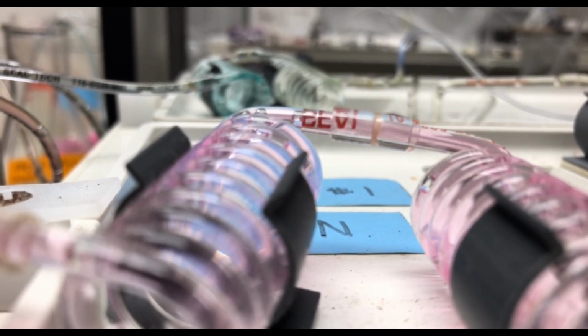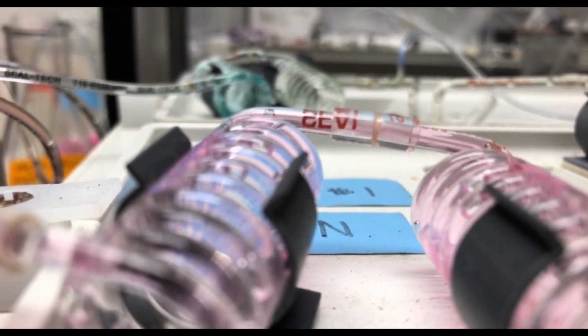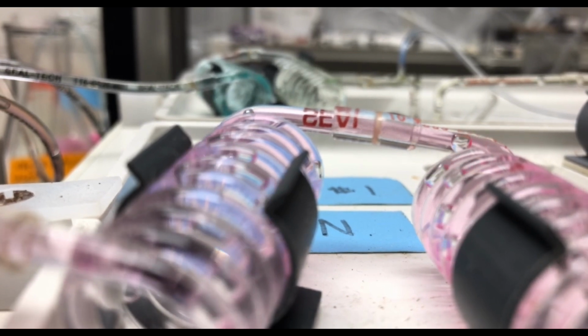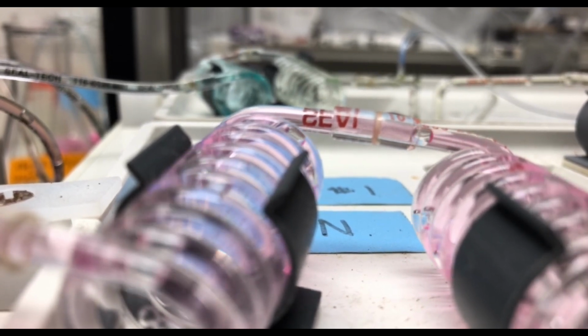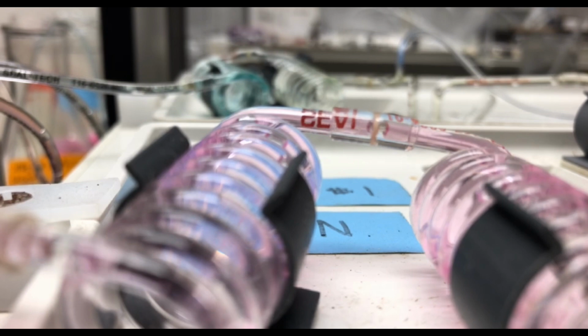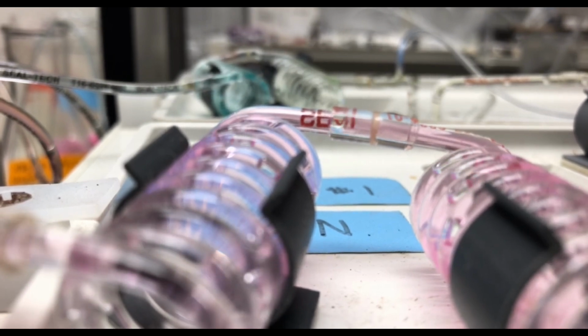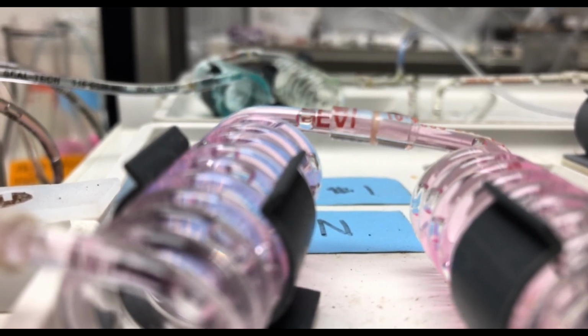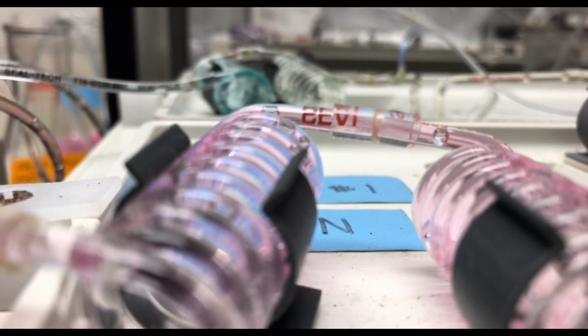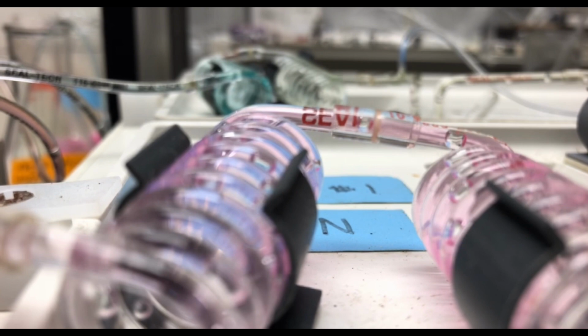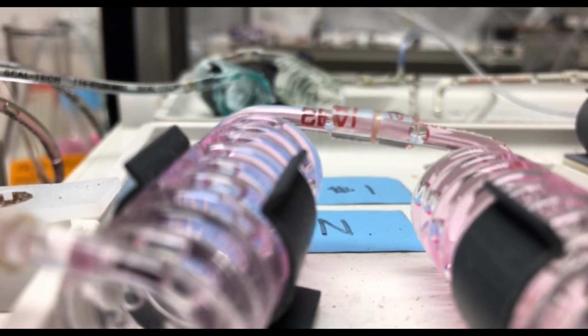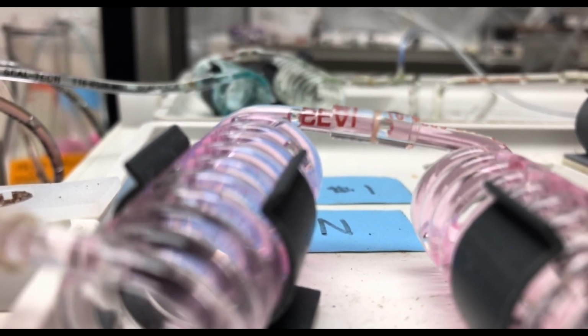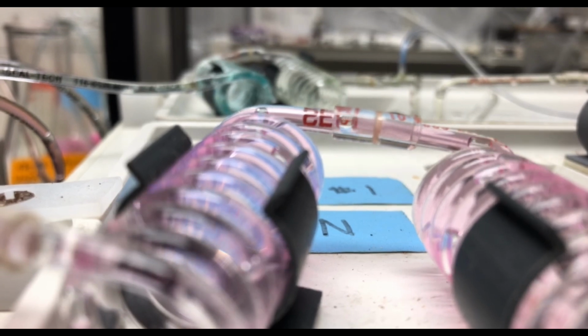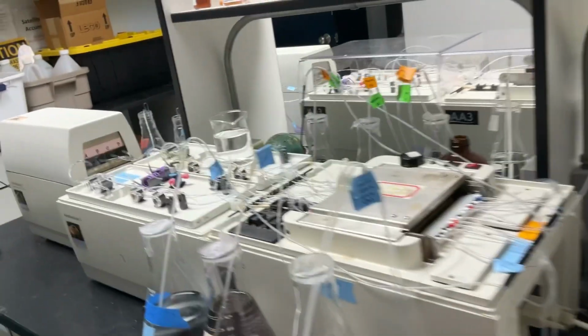So our samples have a lot of nutrients in them, or maybe they have a very little bit of nutrients in them, and the way that we're actually going to detect that is quite similar to the use of a pH strip, which is through color change. So basically, we're pumping through a lot of colorless liquid through this system, and by interacting with the nutrients that we're trying to quantify, it actually exerts a color change that can be detected by a sensor and displayed on a screen. So I'm going to show you what that looks like right there on that screen.